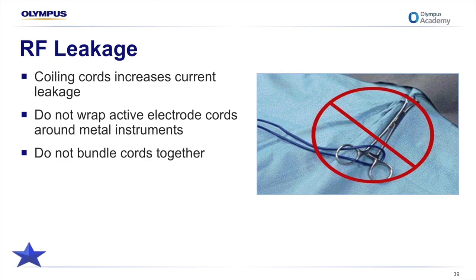Radio frequency current, unlike the 50 cycle current from the wall outlet, can and does leak through the insulation on the cord or the electrode. No matter how thick the layer of insulation is, there will be some current leakage with the use of this high frequency current. The higher the voltage, the more insulation it can overcome, resulting in a higher amount of leakage current. Consequently, avoid wrapping active electrode cords around metal instruments and bundling cords together.